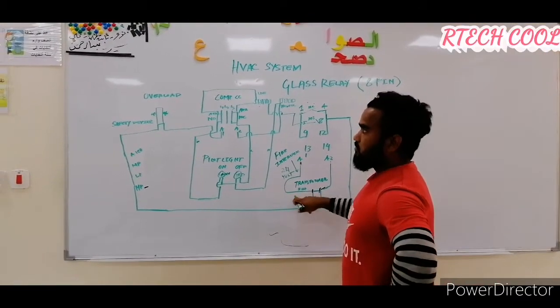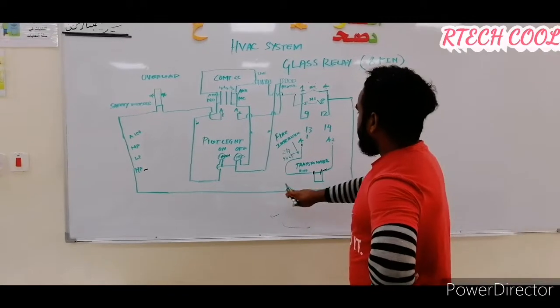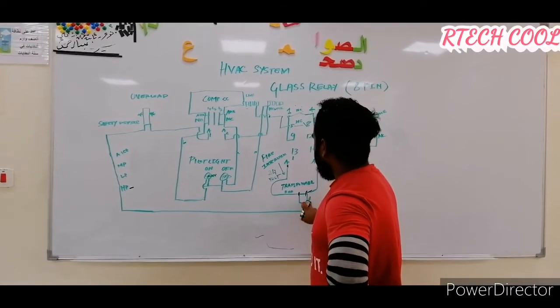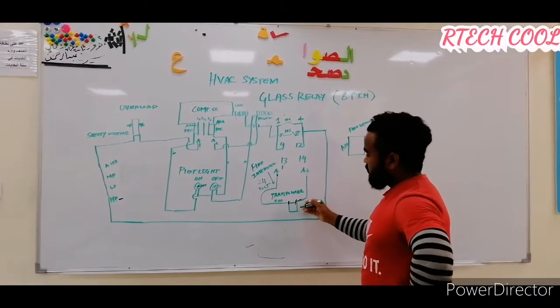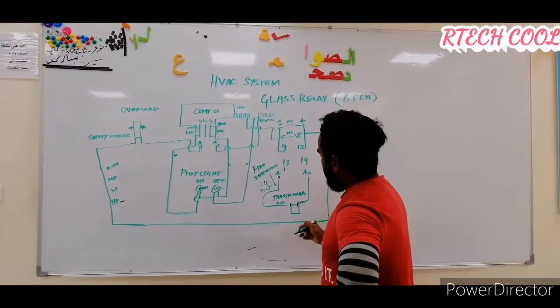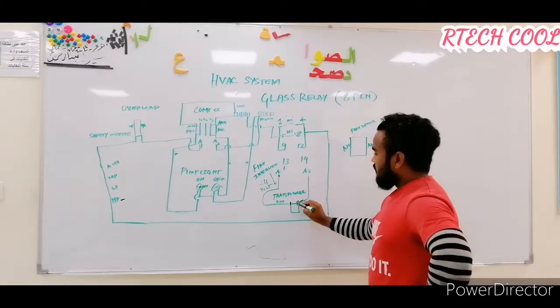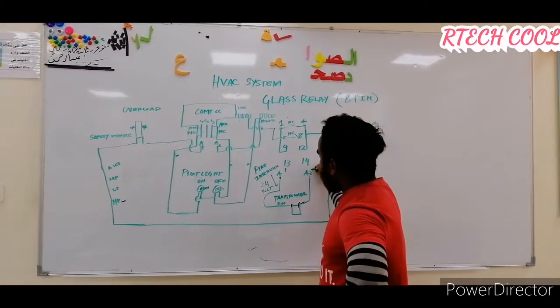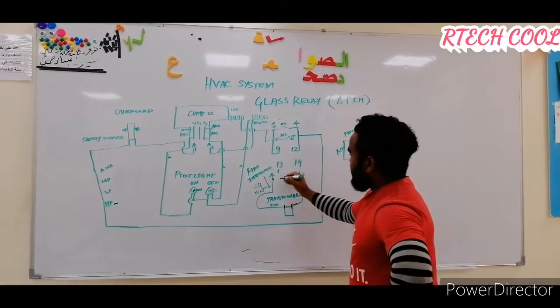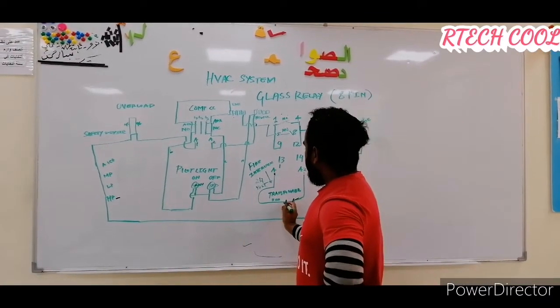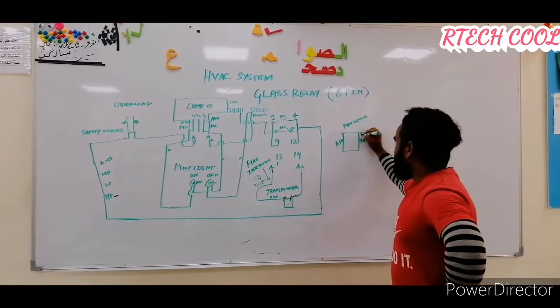There is a transformer. We are using a 24-volt step-down transformer. We put 220V line and neutral here, and it will step down from 220V to 24V. From the 24V output, there are 2 points — one is neutral. We put neutral here at A2, which is point 14. From point 13, we put the line into the NC point.